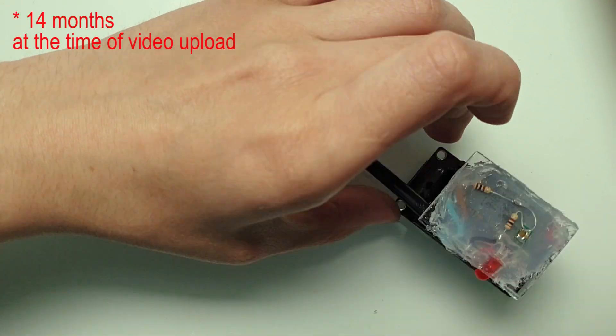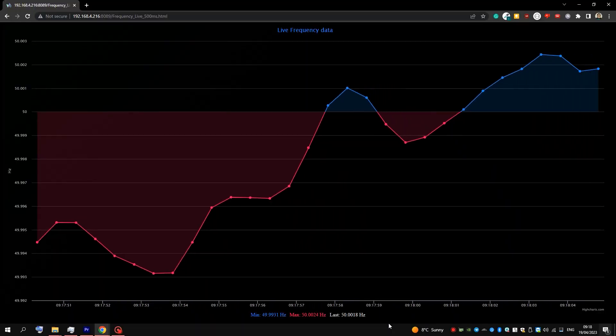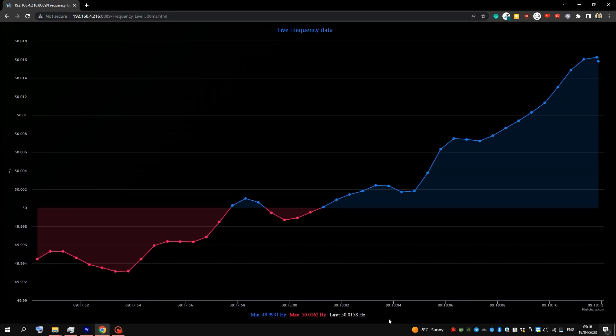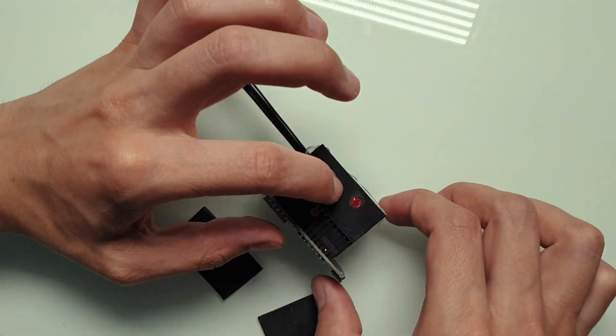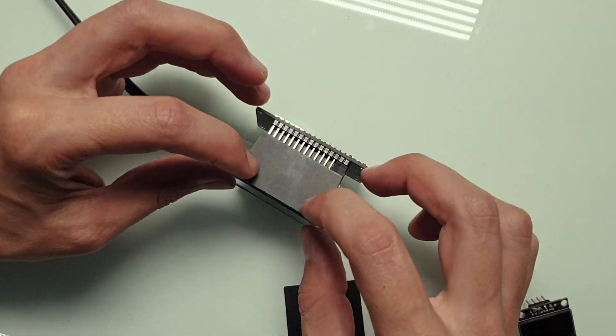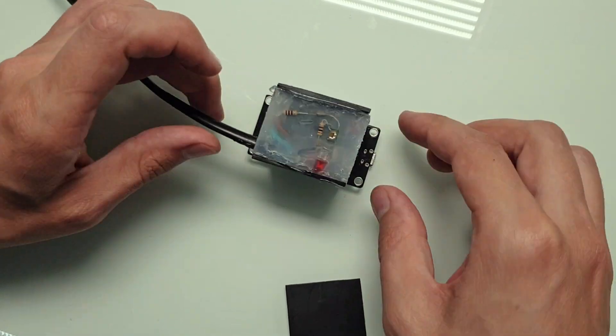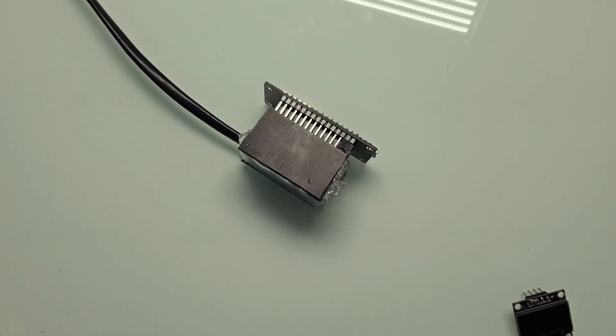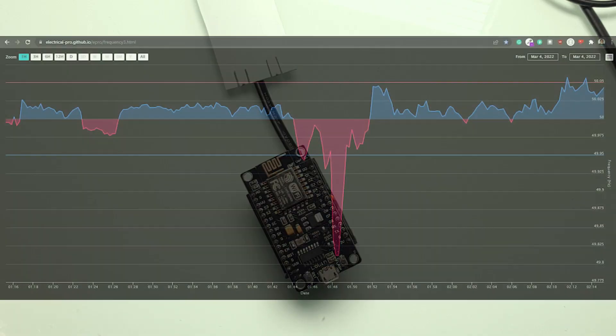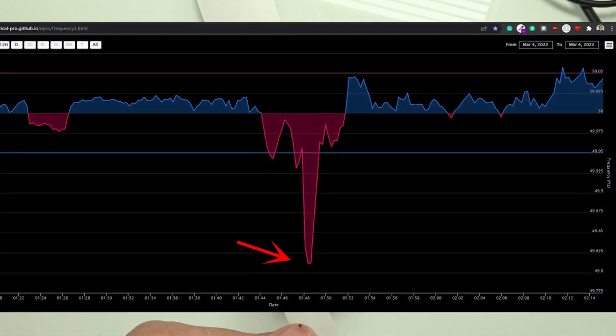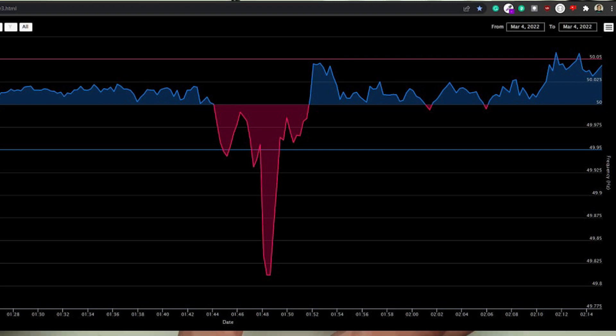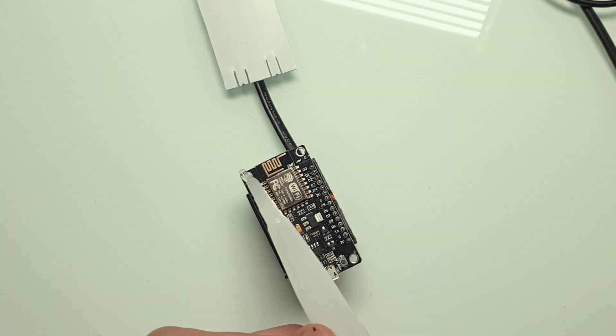I'm using this device for the last 10 months. And for those who don't know, I'm from Ukraine, and my country is going through war. So I detected a lot of historical events with this device. One of the most noticeable events happened on March 4th, when Russia occupied the Zaporizhzhia nuclear power plant. During that night, I detected the lowest frequency that I ever saw. It was 49.8 Hz. Very low frequency in the power grid usually means a sudden loss of generation capacity in the power grid. And it makes sense.